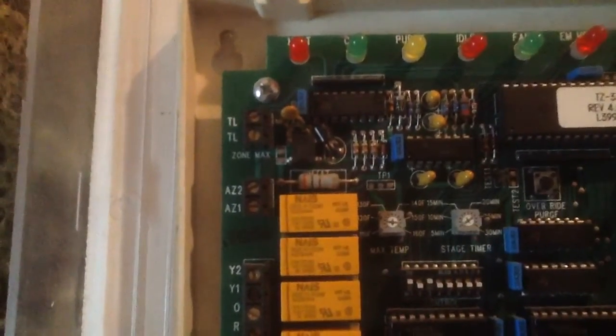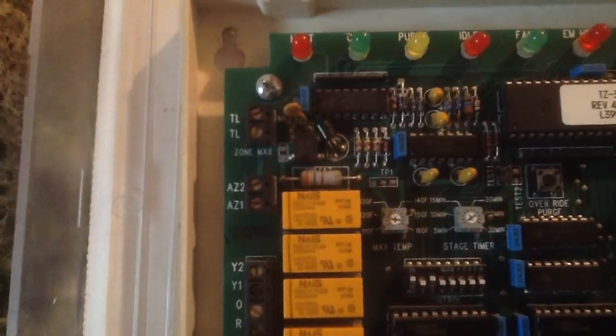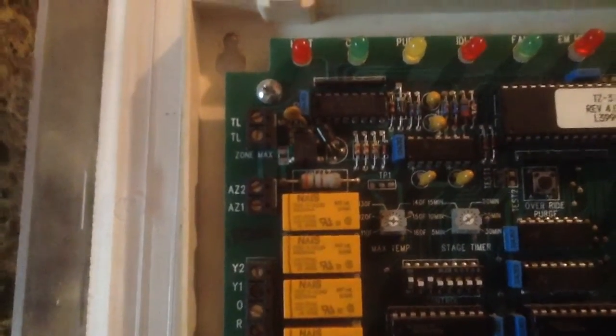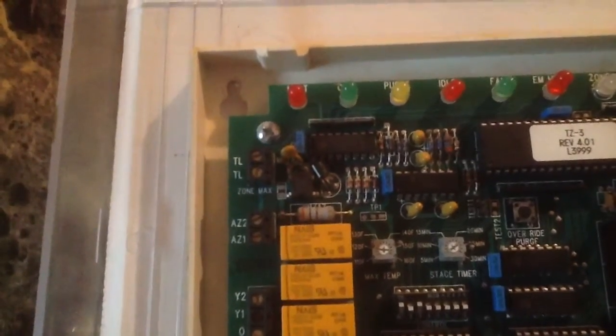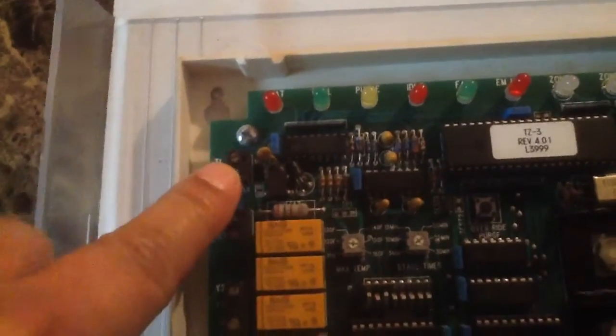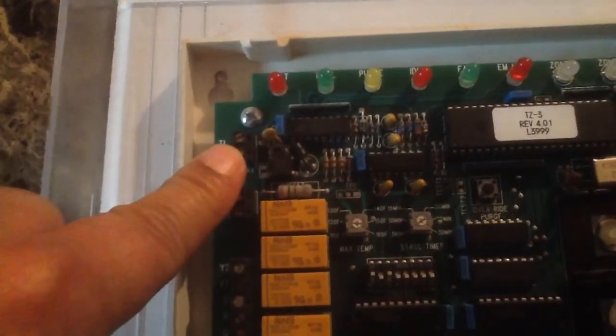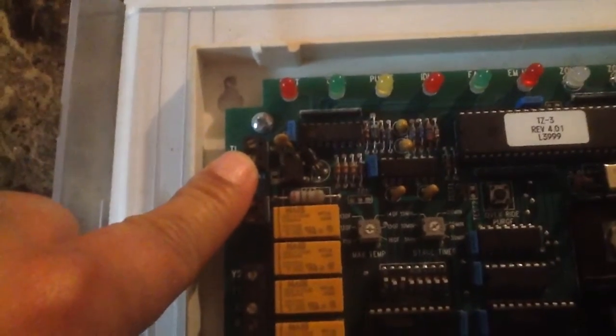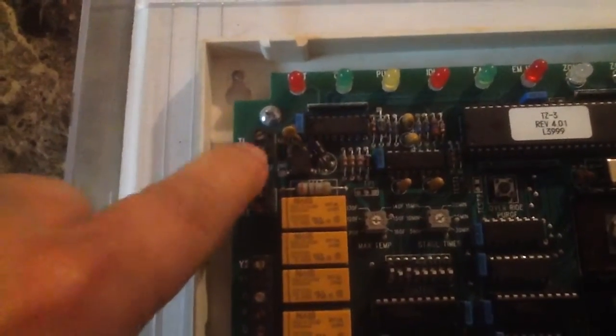And then you got a couple potentiometers here, guys. You'll notice one says max temperature, the other one says stage timer. Max temperature, that's going to be your discharge sensor limit. Typically you'll have a temperature limit for the main limit on the furnace. You want the system, through the discharge sensor, to cycle the system off prior to exceeding the main limit, because if you exceed the main limit, you're going to go into a lockout. So that's what that's there for.